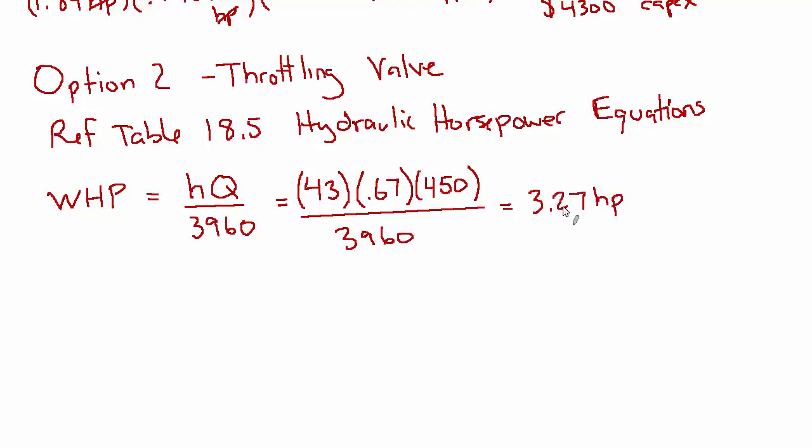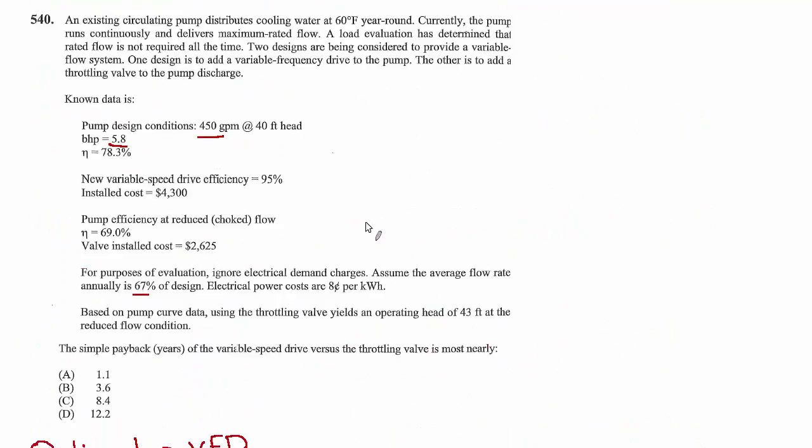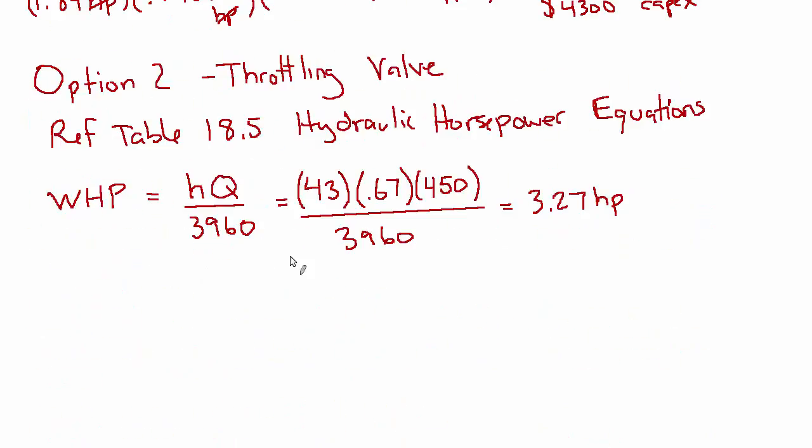And that gives us 3.27 horsepower. And that's the water horsepower. And that is lower than 5.8. So it is worth it, there are going to be savings here. Unfortunately, the efficiency also gets lower in this scenario. It was 78.3% efficient in the original design. But now with the reduced choke flow, it's only 69% efficient. So as we go from water horsepower to brake horsepower, we have to include that efficiency. So the brake horsepower equals the water horsepower divided by the mechanical efficiency of the pump. So that's 3.27 over 0.69. And that gives us 4.7 BHP.